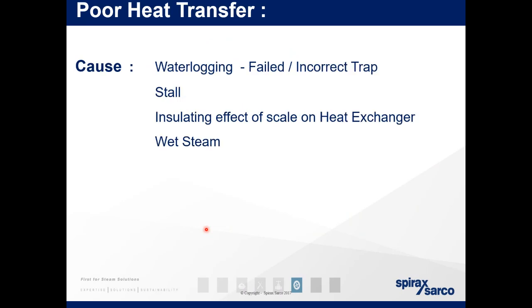So the cause could be waterlogging, incorrect trap selection, stall, as we've said already, the insulating effect of scale on the heat exchanger, and wet steam. So wet steam will have a lower enthalpy.